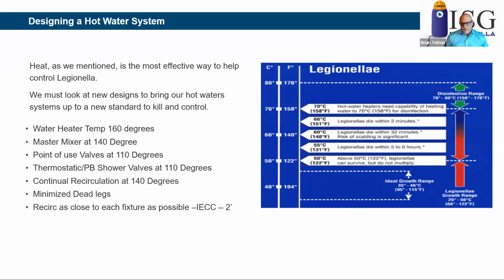So now we're changing our mindset and getting our temperatures up higher, to 160 degrees at the tank, at the temperature distribution point from the mechanical room, then going to a master mixing valve, and down through point-of-use valves and thermostatic shower valves, tying them together, and recirculating at a much higher temperature. This gets most of our piping out of that ideal growth range of 95 to 115-120 degrees. This is an ongoing process, and when you have old infrastructure it becomes a big issue on how we do this, but it's something we have to be aware of and work toward.